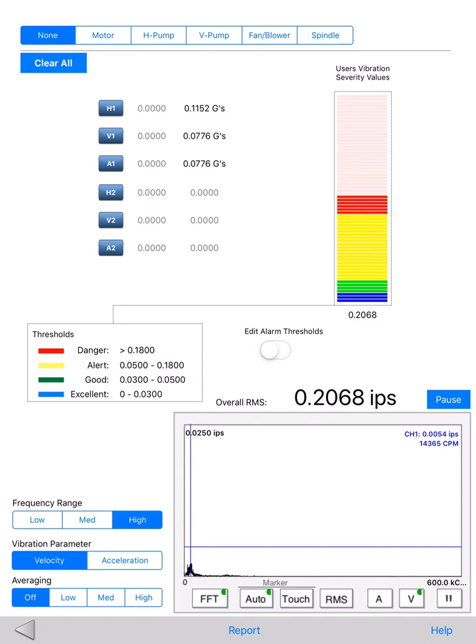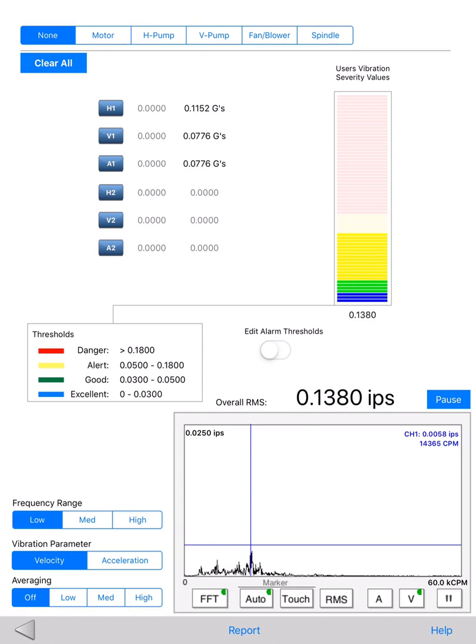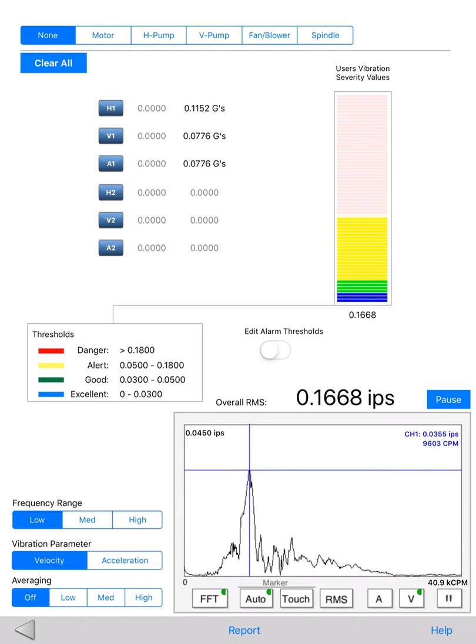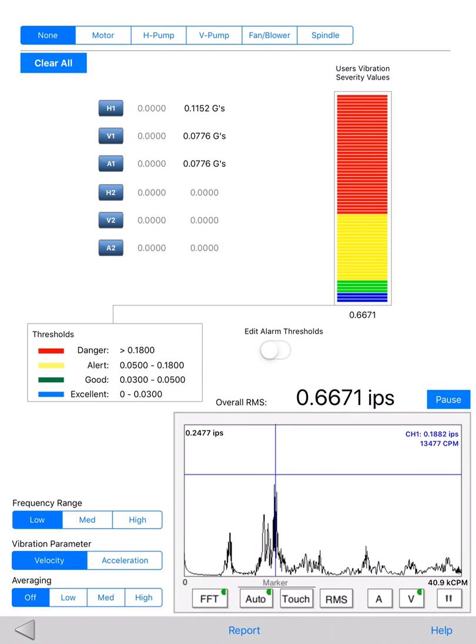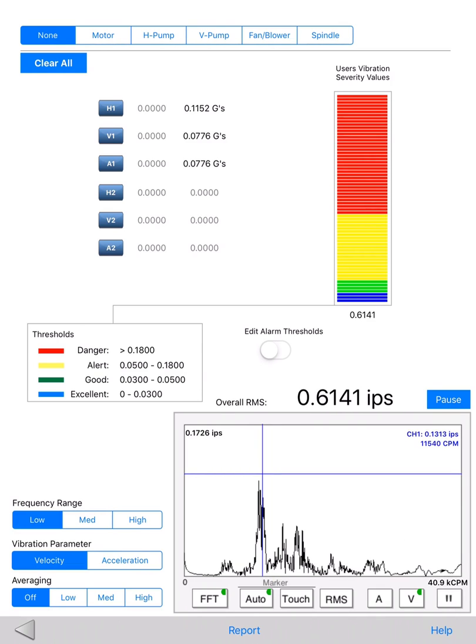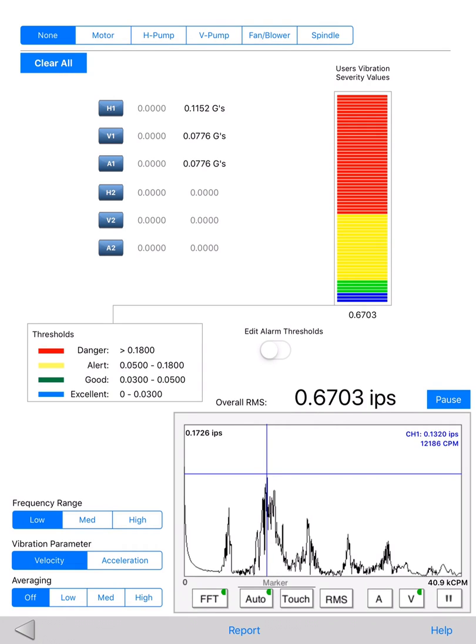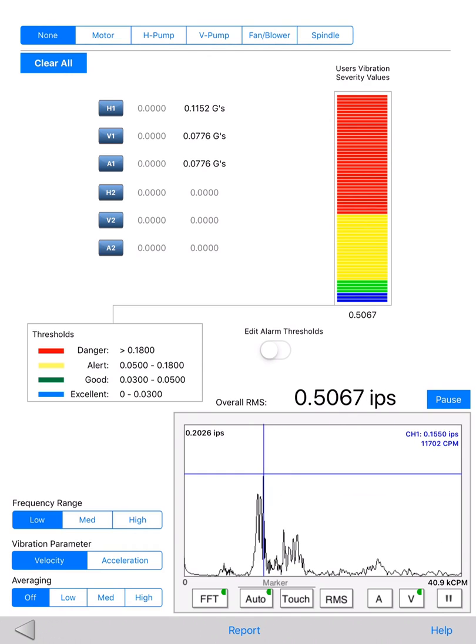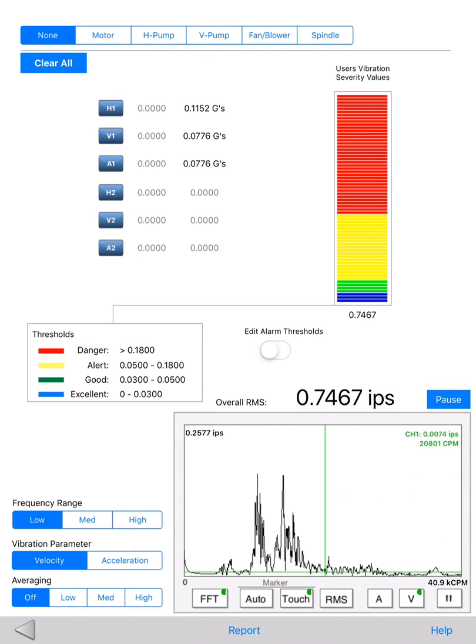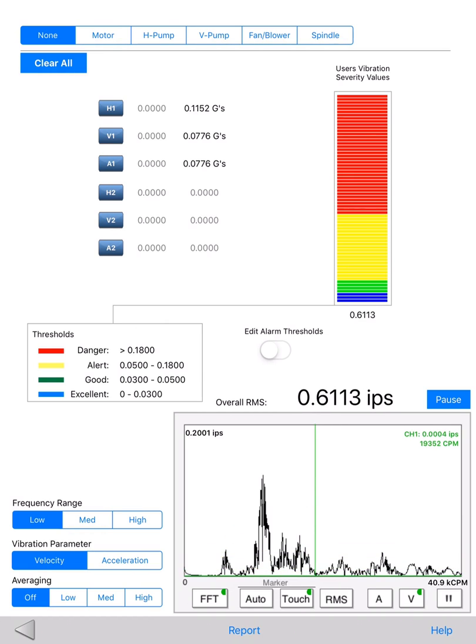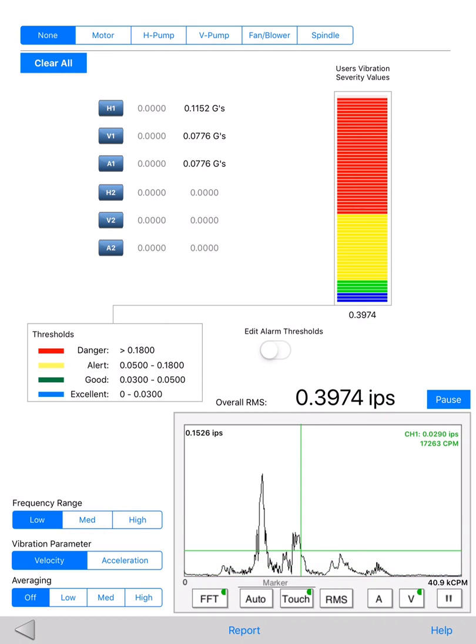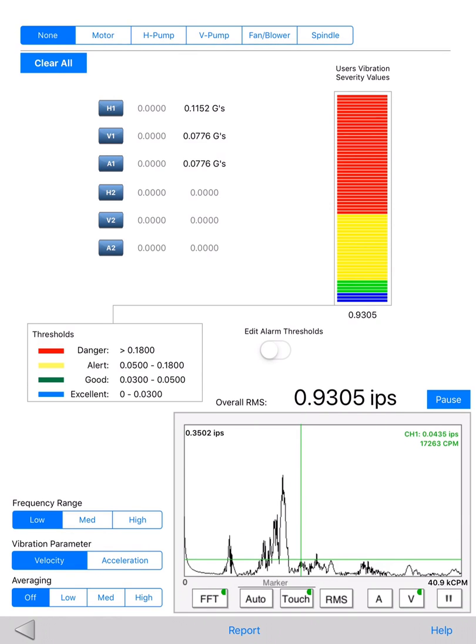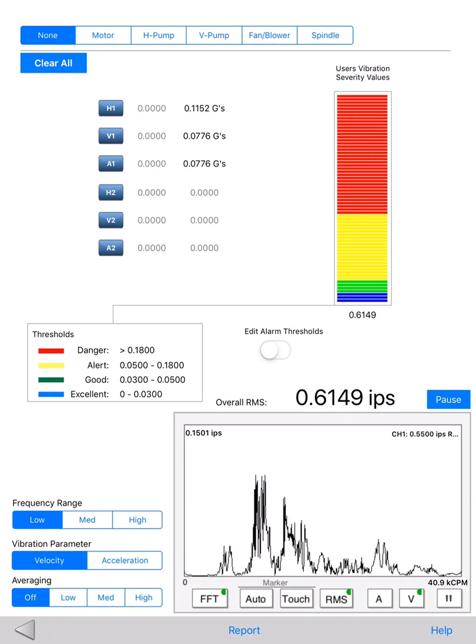There's a peak marker in the FFT spectrum. When it's set to auto mode, i-Vibrometer automatically detects the high peak and places the marker there. When it's set to manual mode, you can move the marker directly with your finger on the signal viewer. Vibration information, including peak amplitude, 1x frequency, and RMS value, are displayed on the top right corner of the viewer.